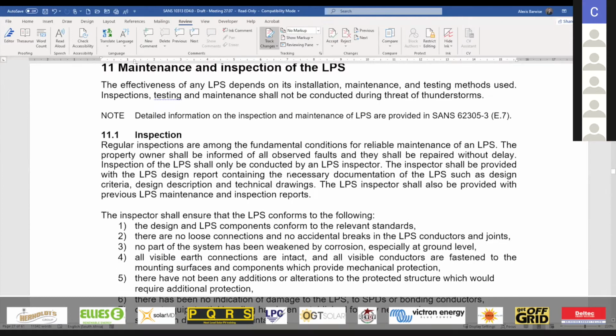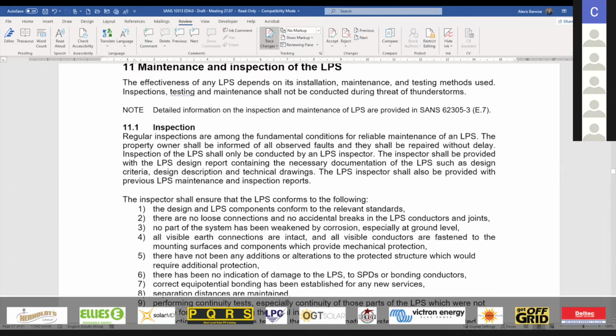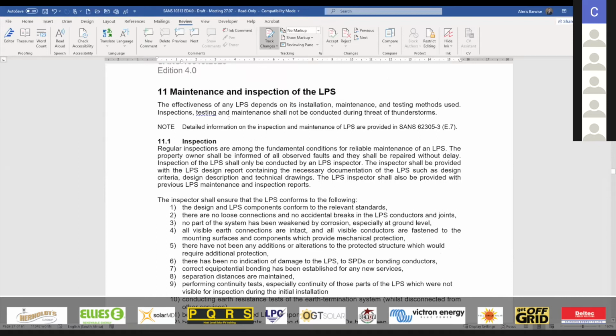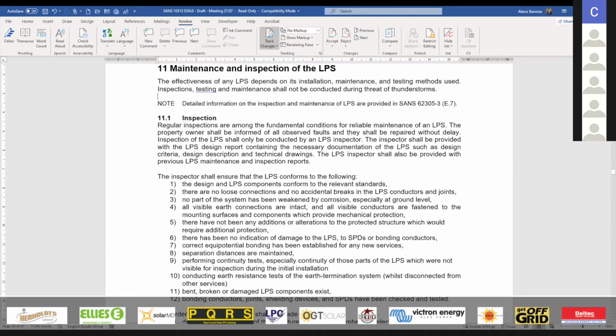Then there is the maintenance inspection of lightning protection systems. Always a topic, always a question that comes up is how often, what must we look at, who should be doing it, etc. So we have a very clear section about the inspection, what needs to be inspected and commented on, SPDs, etc., connections from the lightning system, testing of the earthing system itself.